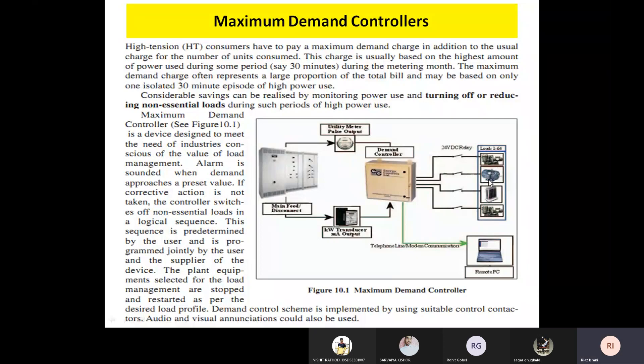The first priority device could be tube lights and fans, then air conditioning. If a machine is running at 100 kW and you are approaching or exceeding 100 kW, the MDC triggers action based on priority programming. The lower-priority devices are disconnected first to bring the demand back within the set limit of 100 kW.